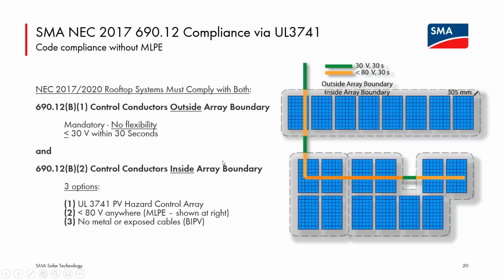As I mentioned, we have an exciting update on the CORE1. There is a listing process from UL, the UL 3741 certification, that is related to rapid shutdown as it's specified in the National Electric Code. The inside of the array requirement most commonly is met by voltage reduction. That is very clear to understand.